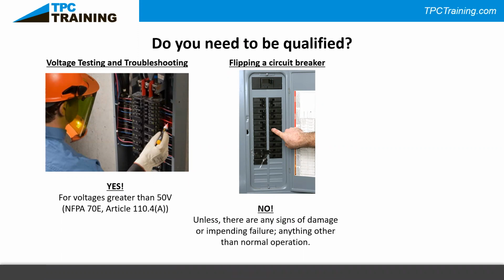Say you walk up to this circuit breaker you're going to flip, and you put your hand up to it and it's hot to the touch. Walk away—someone qualified needs to flip this, because you never know if there's an arc flash hazard behind it. If it's buzzing as you walk up, that's a sign of impending failure and damage to the equipment. You need to be qualified before you operate that circuit breaker.